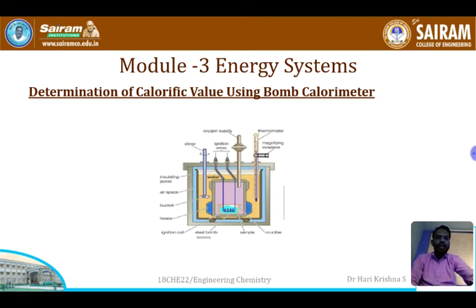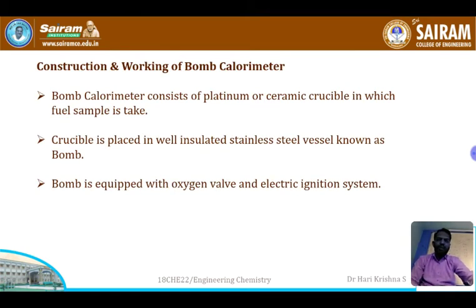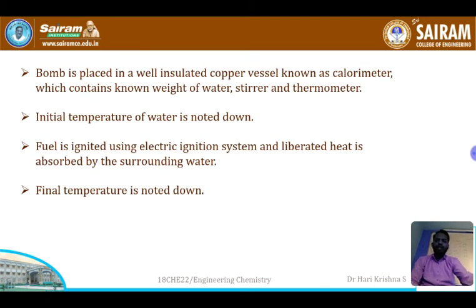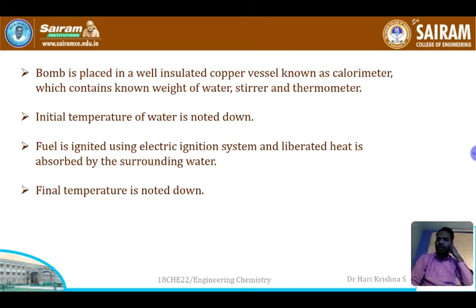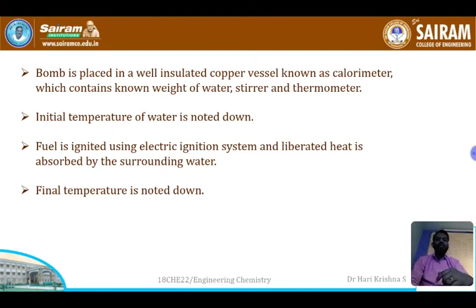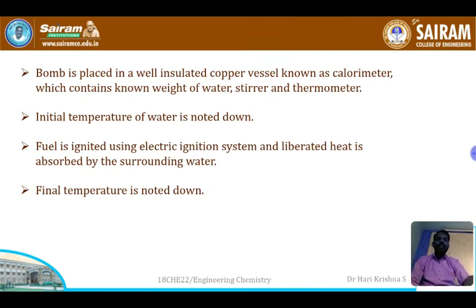Now let us see how the calorimeter works. First, a known weight of fuel is taken in the ceramic crucible. Before igniting the fuel, the initial temperature of the water is noted. The fuel is then ignited using the electric ignition system, and heat is liberated. This liberated heat is absorbed by the surrounding water present around the bomb, causing the temperature to rise slowly.